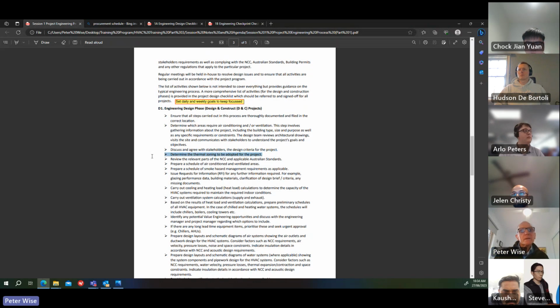Determine the thermal zoning to be adopted for the project—these are things we've talked about previously. Review the relevant parts of the NCC and applicable Australian standards to see what applies to this project. Prepare a schedule of air-conditioned and ventilated areas, which becomes a guide for the project. Prepare a schedule of smoke hazard management requirements if applicable—based on the NCC, the type of project, building classification, size, and height, work out what smoke hazard management applies, if any. There might not be any requirements.